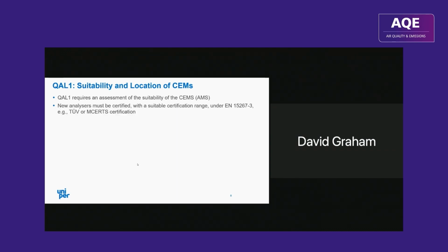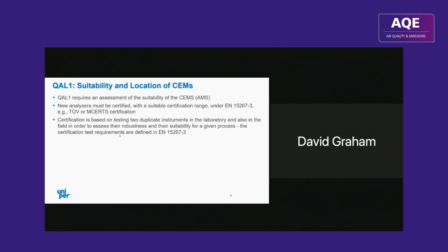QAL 1 is relating to the suitability and location of the CEMs. So it requires an assessment of the suitability of the CEMs. New analyzers must be certified with a suitable range under EN 15267 Part 3. And that certification is based on testing 2 duplicate instruments in the laboratory and also in the field.